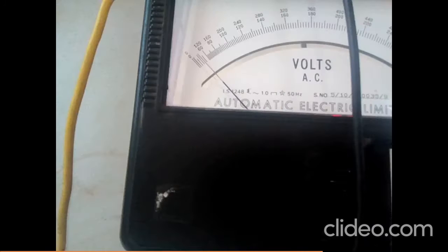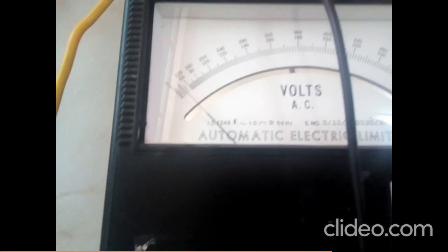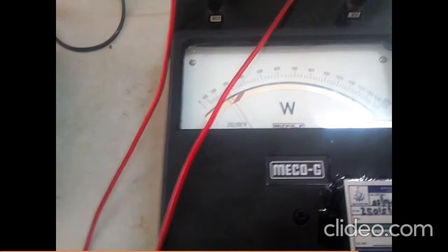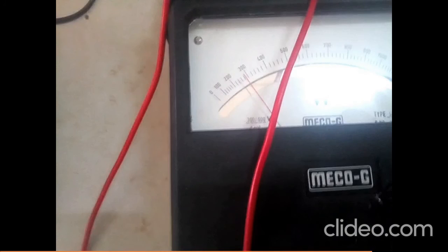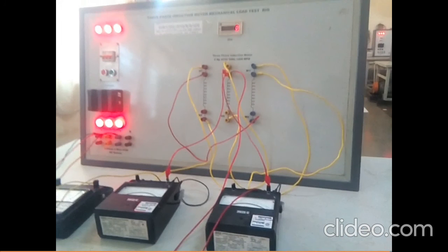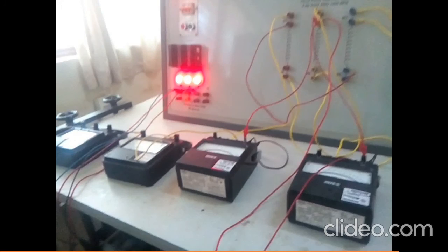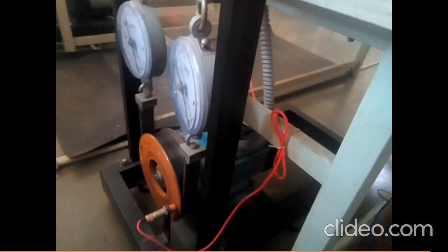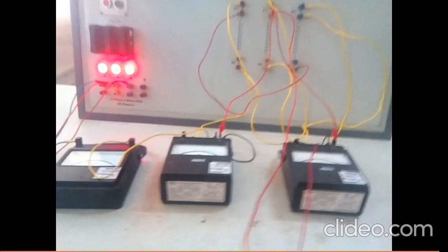With respect to that rated current, we note down the voltage during the block rotor test as well as the power consumed during the blocked rotor test, or short circuit test. This test can also be called a short circuit test, and the readings taken during it are called short circuit readings: voltmeter reading as short circuit voltage, ammeter reading as short circuit current, and the readings from the two wattmeters as short circuit power. These should be taken.